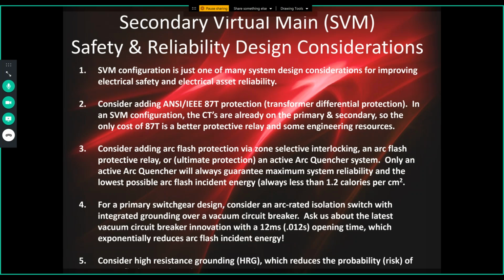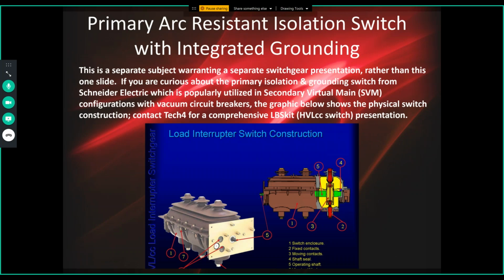And then on the secondary, whether you have a secondary virtual main or a physical main, it doesn't matter, we would always recommend, when meeting the NEC requirements, high resistance grounding. According to IEEE, high resistance grounding doesn't reduce arc flash incident energy, but reduces the probability of an arc flash occurring by at least 95%, because at least 95% of arc flash events begin as single phase ground faults. And I wanted to show you a picture of that isolation and grounding switch I mentioned earlier.